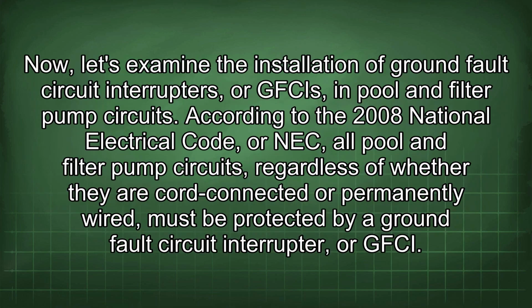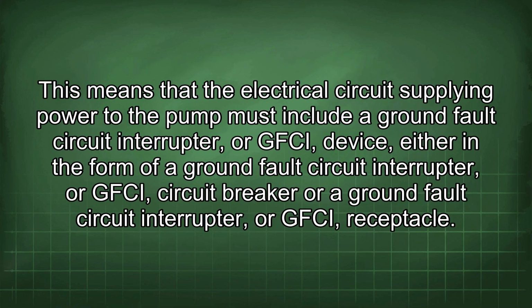Now let's examine the installation of GFCIs in pool and filter pump circuits. According to the 2008 National Electrical Code, or NEC, all pool and filter pump circuits, regardless of whether they are cord connected or permanently wired, must be protected by a GFCI. This means that the electrical circuit supplying power to the pump must include a GFCI device, either in the form of a GFCI circuit breaker, or a GFCI receptacle.